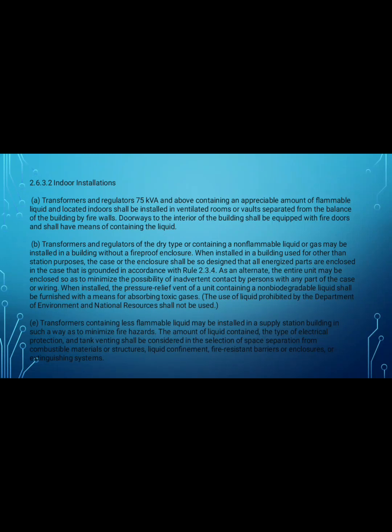2.6.3.2 Indoor installation. A. Transformers and regulators 75 kVA and above containing an appreciable amount of flammable liquid and located indoors shall be installed in ventilated rooms or vaults separated from the balance of the building by firewalls. Doorways to the interior of the building shall be equipped with fire doors and shall have means of containing the liquid. B. Transformers and regulators of the dry type or containing a non-flammable liquid or gas may be installed in a building without a fireproof enclosure.